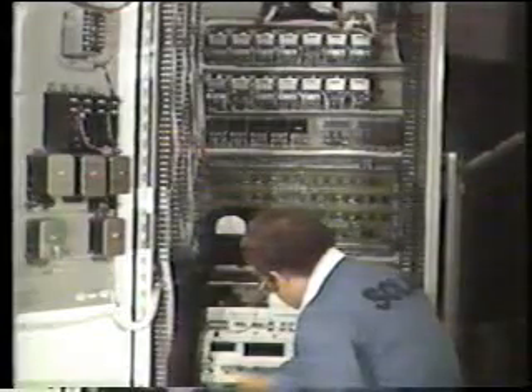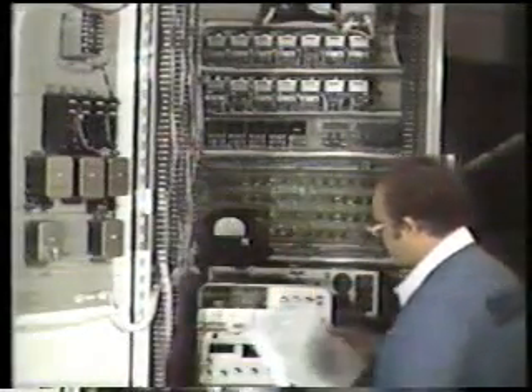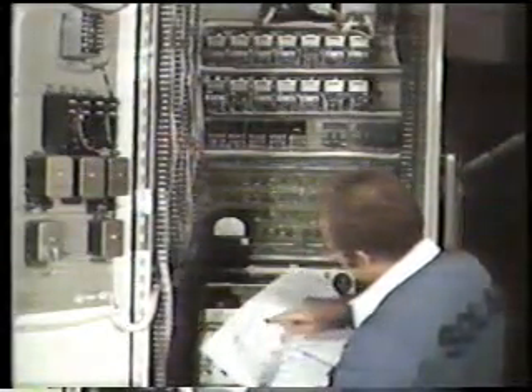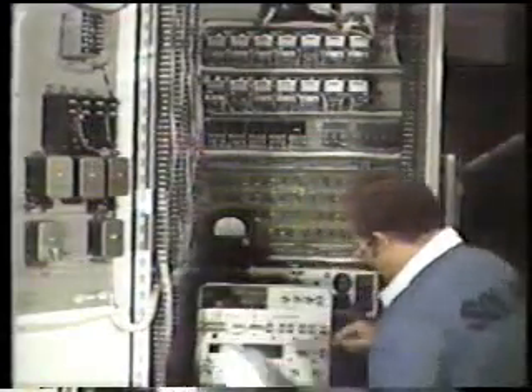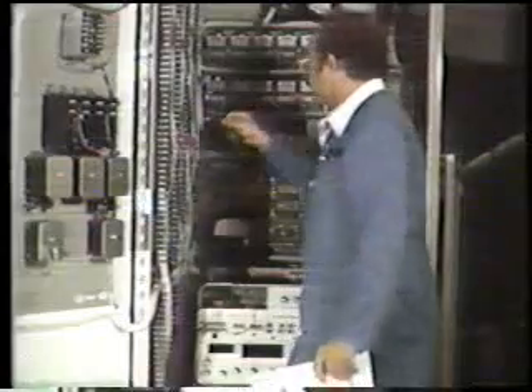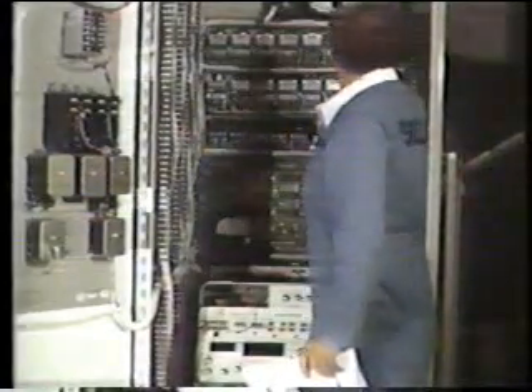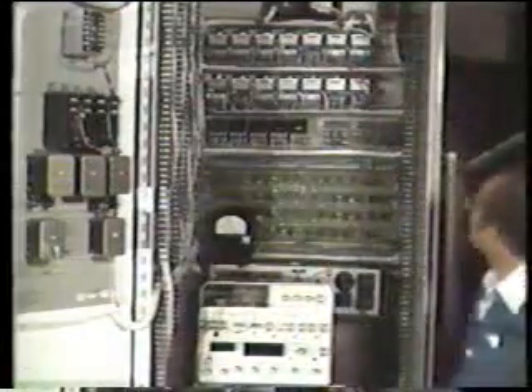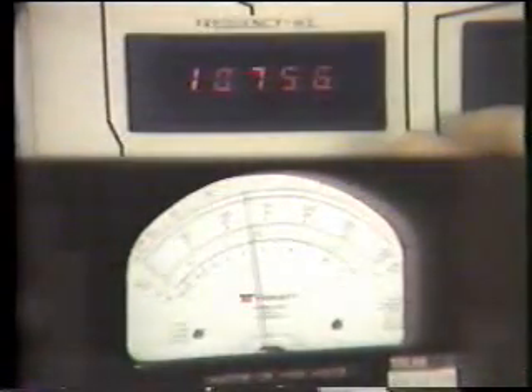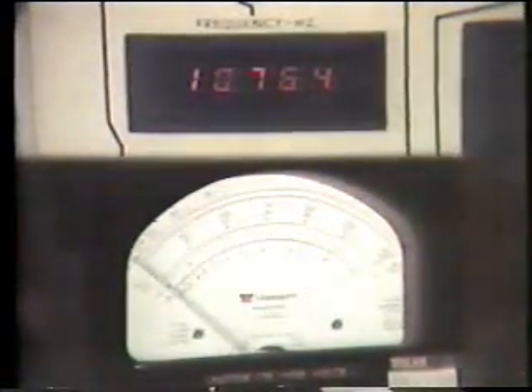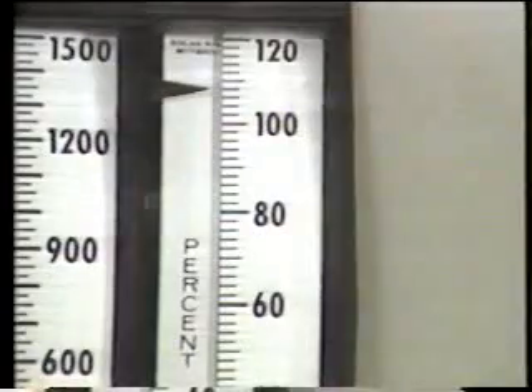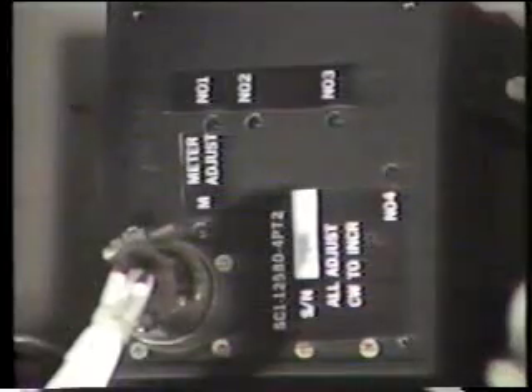Note that the 108% speed switch uses both normally open and normally closed contacts. The correct operation of both sides of the contacts should be verified. Move the VOM test leads to check the other set of 108% contacts. Adjust the frequency output until transfer occurs. Observe the VOM for transfer indication. Check the speed meter. It should read 108% speed. If both sides of the switch do not transfer, the control unit must be replaced. Recheck the set point after each adjustment.